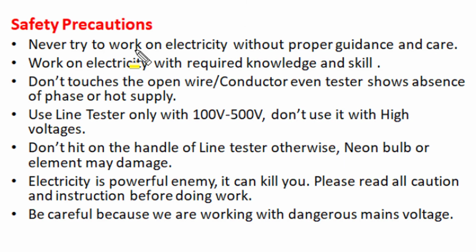When the line tester is used in domestic distribution supplies, even that supply voltage is dangerous, and proper safety precautions and protective measures are required to handle the line tester. If the electric circuit is very difficult and we have little awareness about its functioning, then one should not work on such an electrical circuit without proper guidance or care. One must work on an electric circuit only with the required knowledge and skill for that fault finding or repair action. Even if a phase tester or line tester shows absence of glow, an indication that the touched position doesn't have phase or hot supply, even in that condition one should not touch those open wires or conductors.